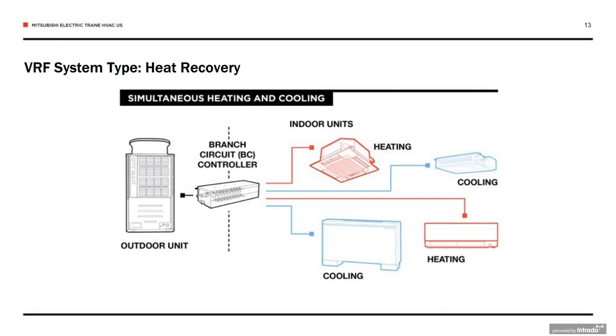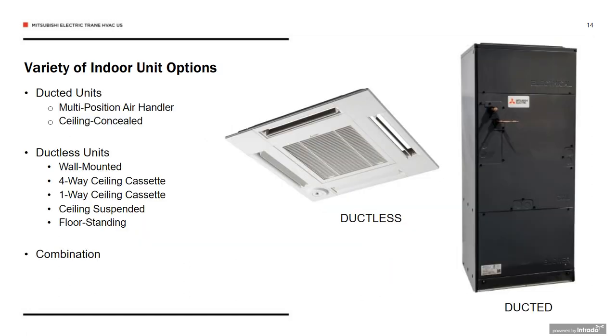Next, we look at a heat pump with heat recovery. This system consists of an outdoor unit, an indoor unit, and a branch circuit controller. This allows for simultaneous heating and cooling, where one unit will be in heat and the other one will be in cooling, as depicted here. Now, the biggest difference that you'll see between the heat pump and the heat recovery option is the branch circuit controller. The branch circuit controller allows for the system to deliver the refrigerant in the right mode to the indoor unit that's calling for heat or the indoor unit that's calling for cooling. Essentially, it directs the refrigerant for the communication with the outdoor unit and the indoor units to provide the application for that zone that you need. And it's ideal for offices, hotels, multifamily, anywhere where the facility needs are diverse.